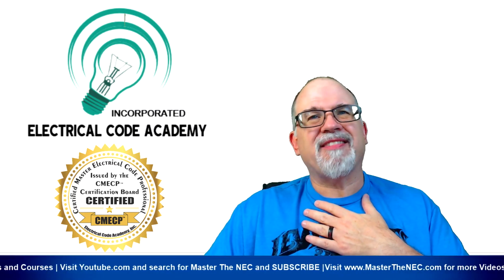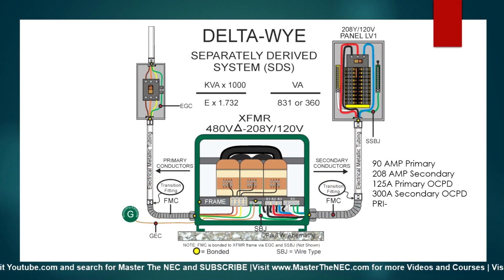For most of us, we're not going to worry about it too much because this is what we normally will see. Okay, so we have our primary protection, we have our secondary protection. Although it is here to protect this panel board, these conductors are sized based on this. This is a 10-foot secondary rule. Then if this is a 300 amp rated device, then these conductors will be rated for 300 amps, even if we know that the secondary of this transformer is not going to put out enough current to be able to handle whatever the load would be.